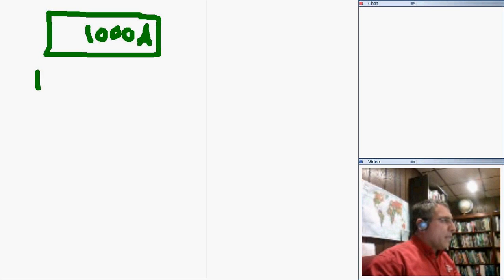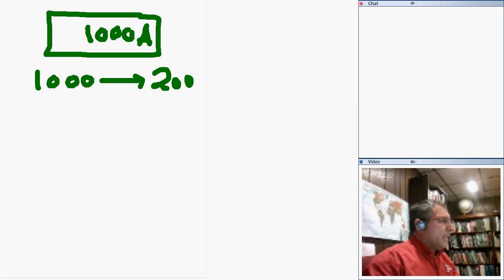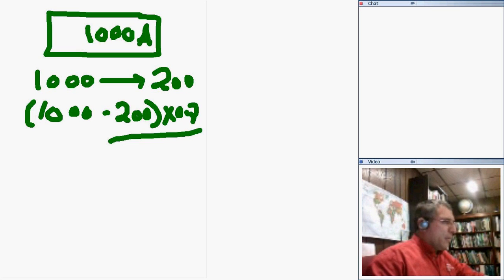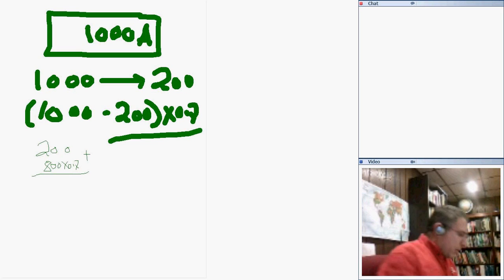I take the first 1000 amp. Remember, you can derate after the first 200. First 200, leave them alone. Then take the 1000 minus 200, 800, and multiply this by 0.7. The 0.7 is coming from 220.61, I believe. So you end up with 200 plus 800 times 0.7, which equals 560, so I have 760 amps. This is the neutral load.